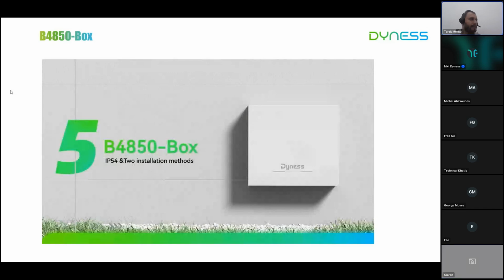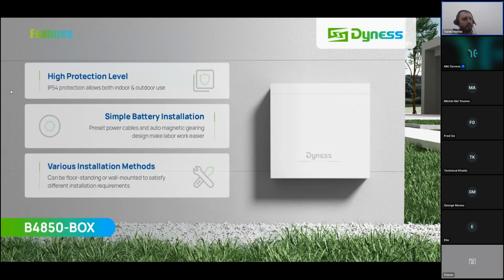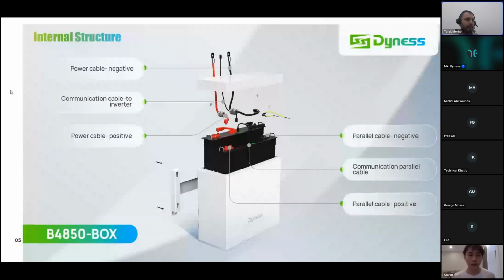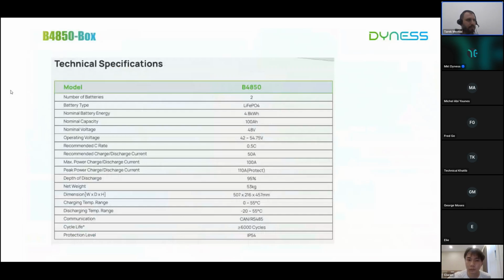Okay, the B4850 has an advantage, which is IP54 protection. It can be used for indoor or outdoor use. Simple battery installation: all this accessory will be included in the package, and various installation methods will be checked. Firstly, the package will include the power cables, the communication cables between battery and inverter, the case, and the accessory for wall mounting.